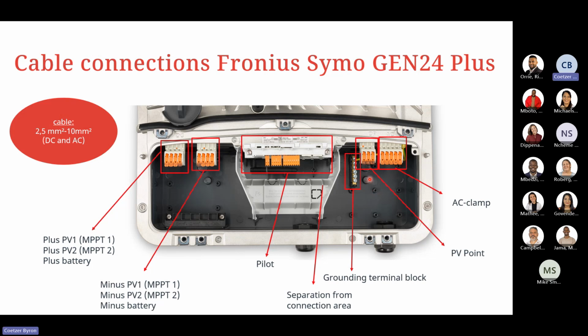And then on the right hand side, we've got our AC connection points. So we've got our AC clamp for our normal grid connection. And then lastly, we have our PV point connection, which is here on the right hand side also. So the PV point is if the client wants to make use of power generation through the unit itself. If there is a power failure and they don't have a battery in this configuration, they can still use the PV point to extract that power from the modules through the unit to a dedicated output that they have located in the house.